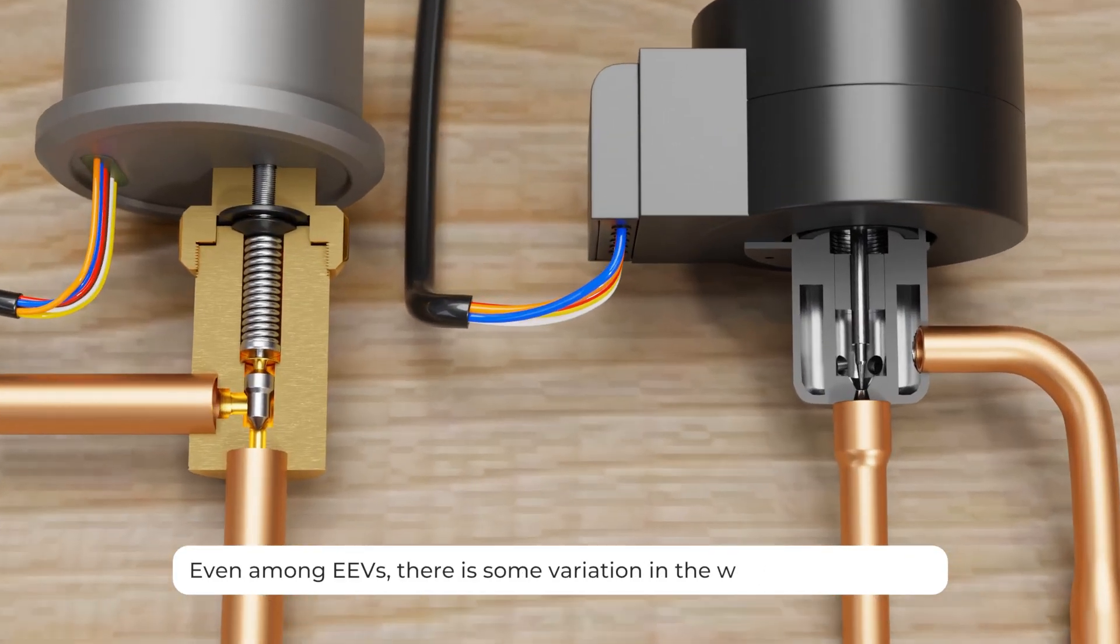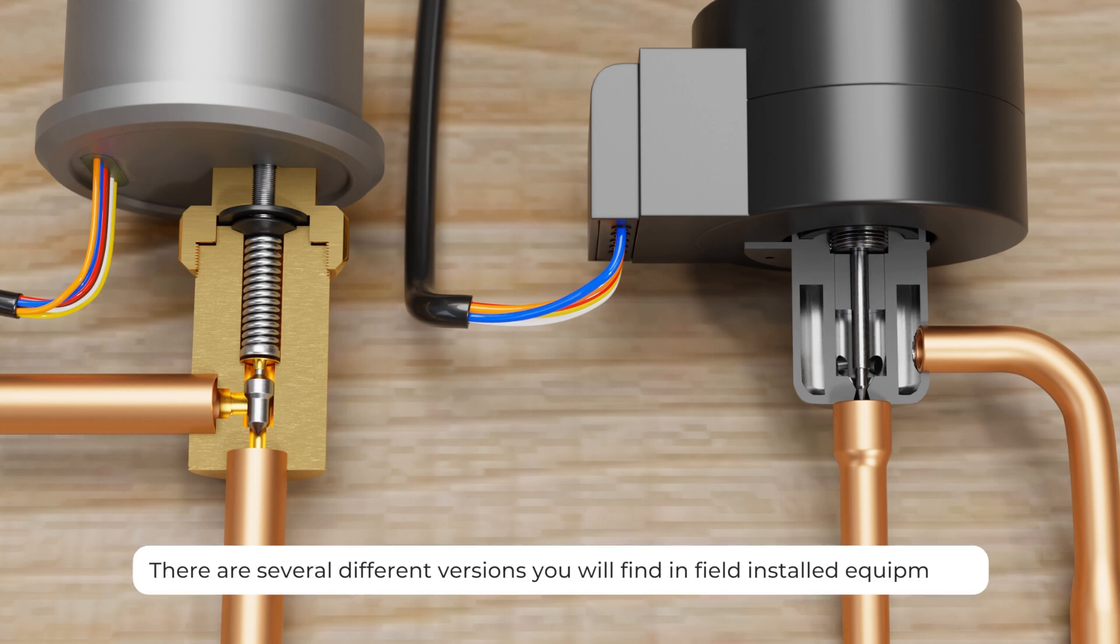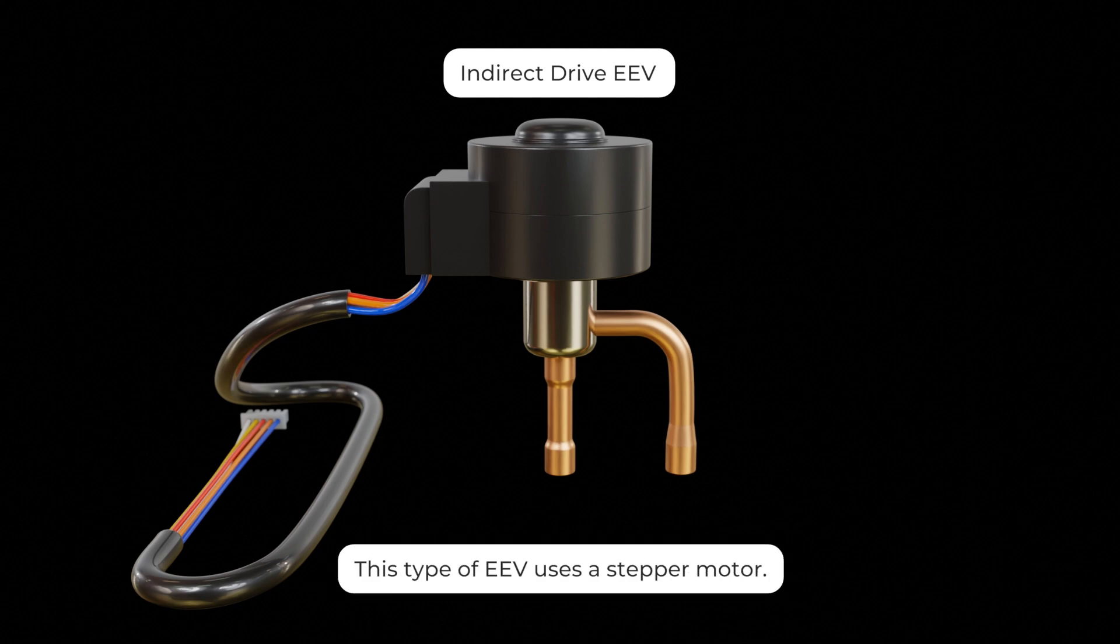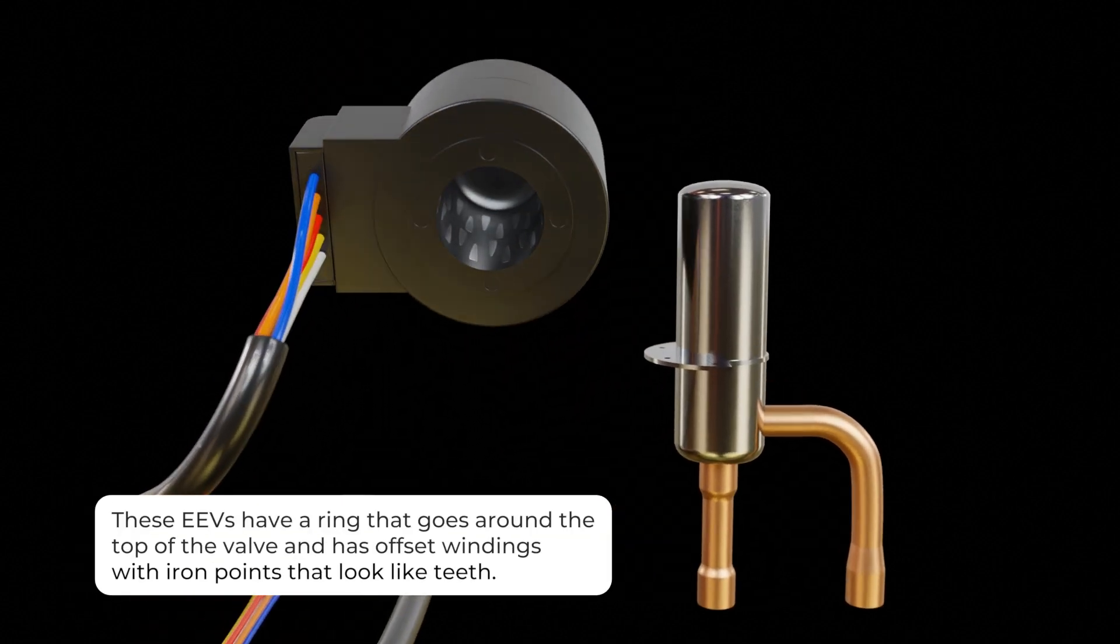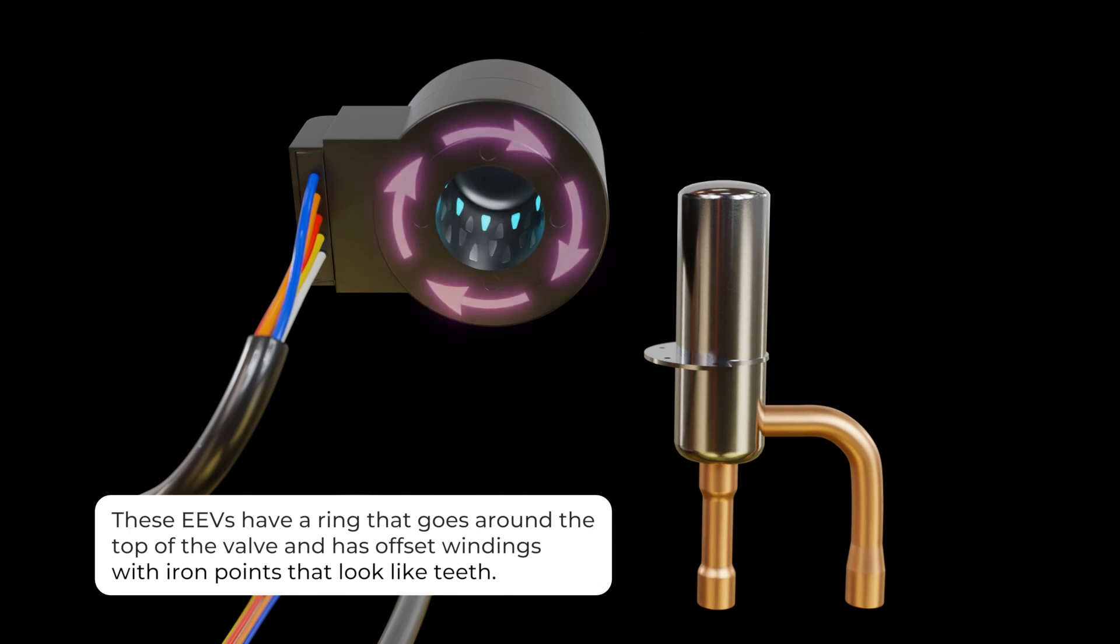Even among EEVs there is some variation in the way they modulate because there are several different versions you will find in field installed equipment. This type of EEV uses a stepper motor. These EEVs have a ring that goes around the top of the valve and has offset windings with iron points that look like teeth.